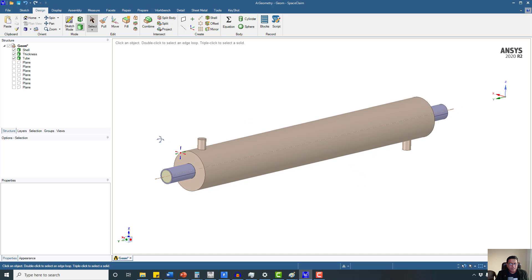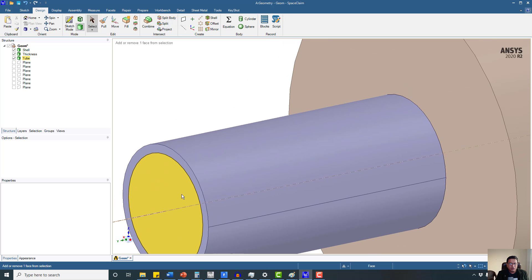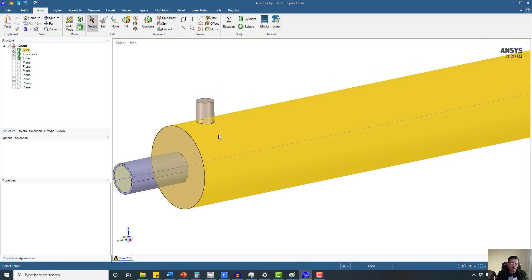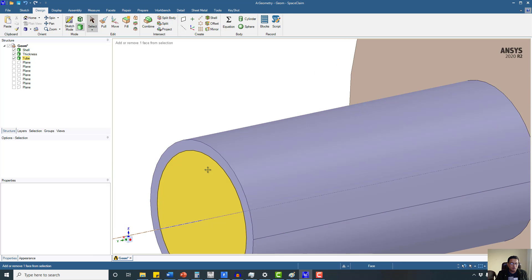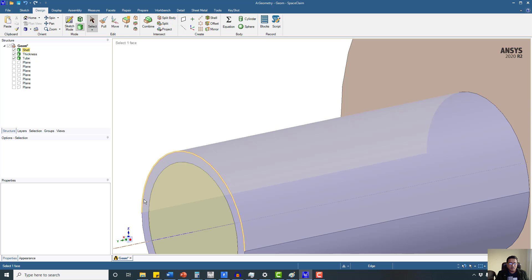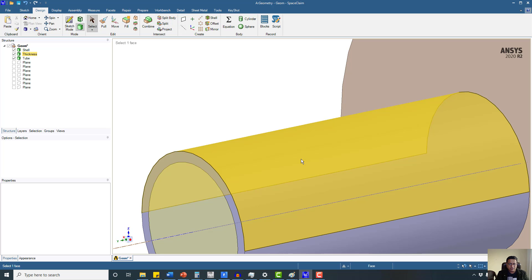This is the shell and tube heat exchanger. We have the shell part and the tube part where we have the cold fluid. In the shell part we have the hot steam that will condense to liquid form, which is common in power plants. The tube thickness serves as a solid body so the heat conducts from the steam in the shell part through to the tube wall, and then this heat is carried away by the fluid flowing inside the tube side.